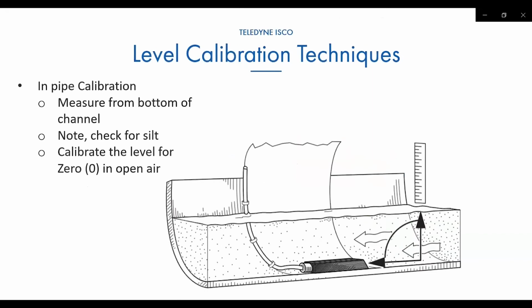Now, for other calibrations, you can just measure in the water. What you want to do is take a ruler and put it directly in the water and measure from the bottom of the channel to the top of the water. You do want to account for silt that may be in there. So part of your programming is you want to tell it that there's 1 inch of silt, so you get the proper area calibration.